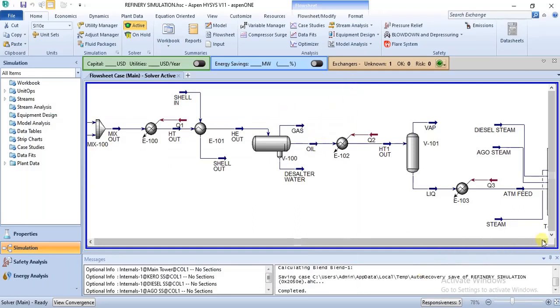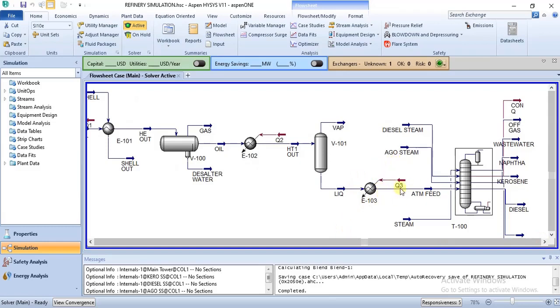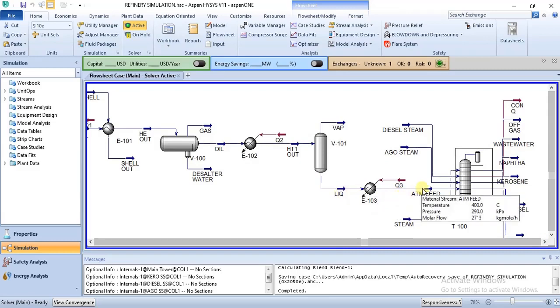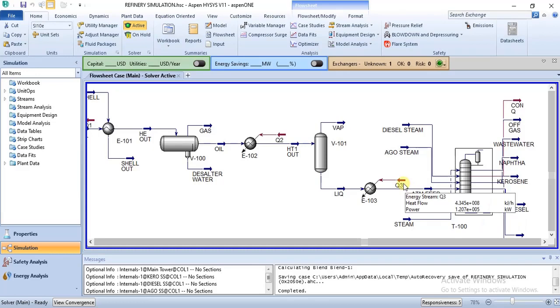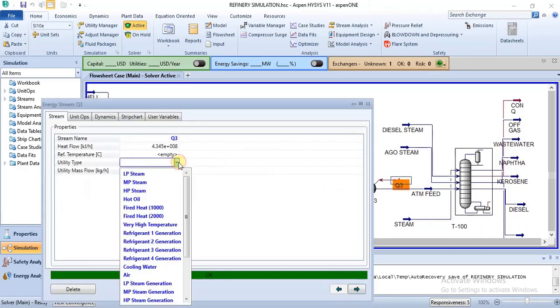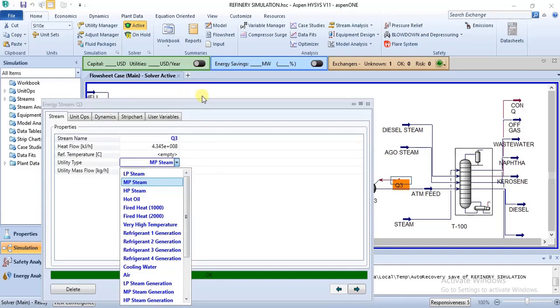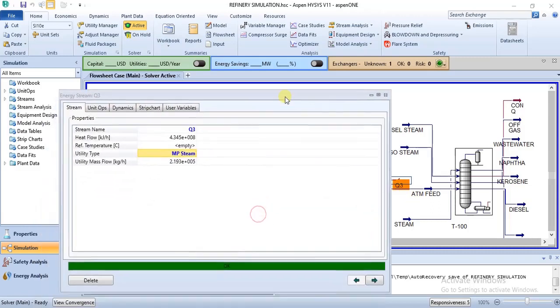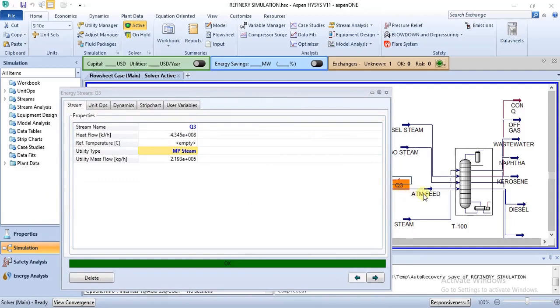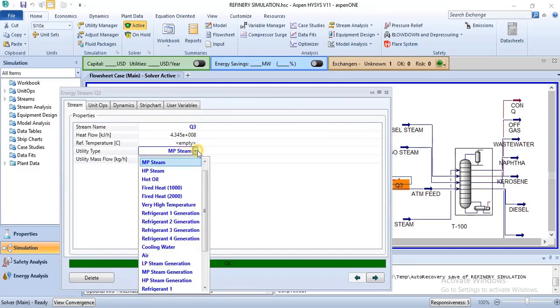Now let's try this other energy stream. This one has a temperature difference of over 200°C — from 175°C to 400°C. That's over 200 degrees in temperature change. For this one, because the temperature change is quite large — from 175 to 400 degrees — I would suggest the use of hot oil.